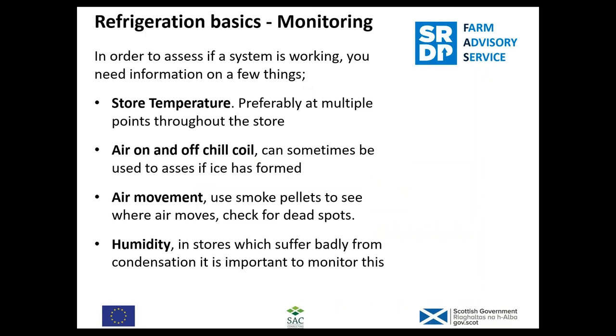Monitoring. The main thing, if you want to make your store efficient, is knowing what's going on in all the different components — because you might think you don't use any defrost but you might find that you actually do. Obviously store temperature, and preferably at multiple points throughout the store. You still get stores with just a little probe hanging from the roof in the middle — unless you've got a very good air circulation system, it's probably not accurate because there'll be huge variation across your store of three or four degrees. So use as many multiple probes throughout the store as possible, especially any dead spots or warm spots. Also monitor the air temperature on and off your chill coil — this can tell you if it's blocking or if there's a problem with a fan.